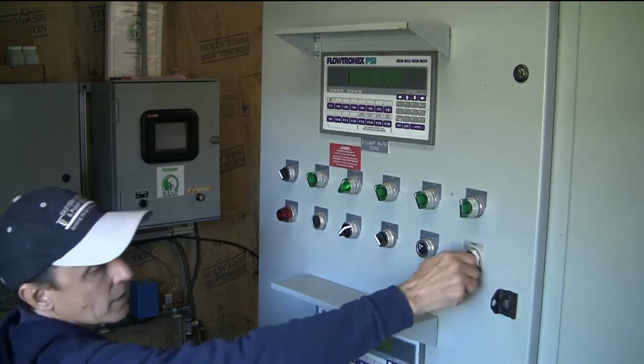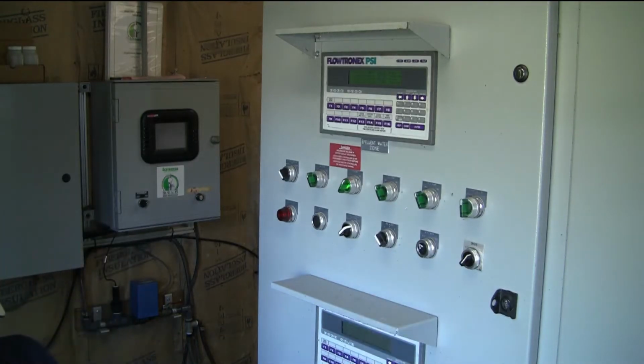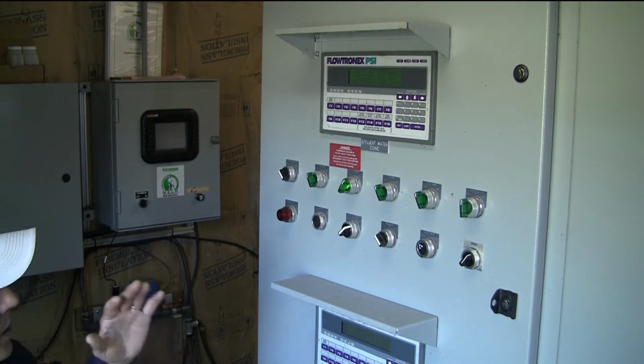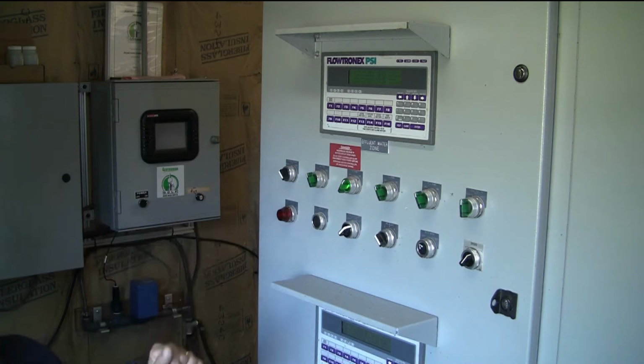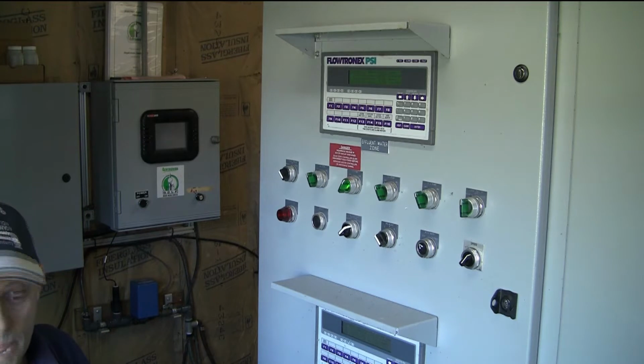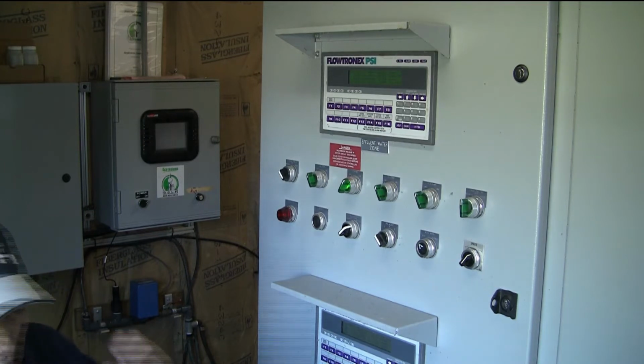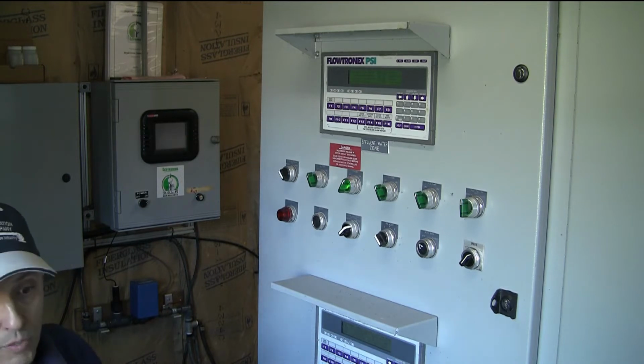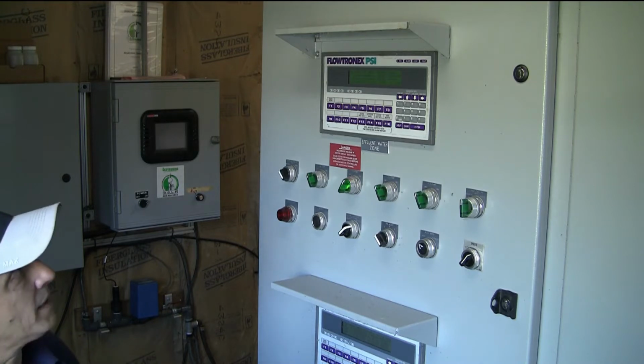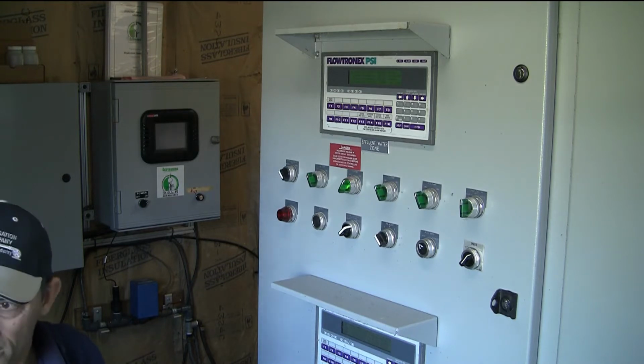Sometimes we like to set it a little higher than the normal standard. 15 pounds is where the high pressure safety is. Sometimes with that pilot valve on the relief, it starts to weep a little bit. When it gets up to like 10 pounds over, it'll start to leak a little bit. You'll hear a lot of dripping in the wet well. We have the drive, which is adjusting the pressure, so it's okay on certain cases to have it set a little bit high.